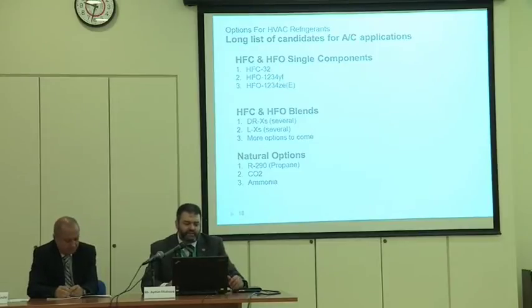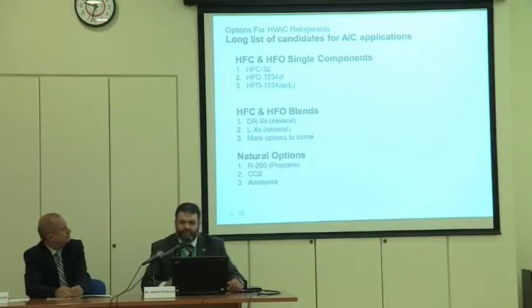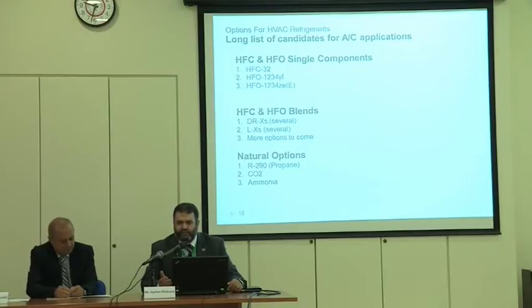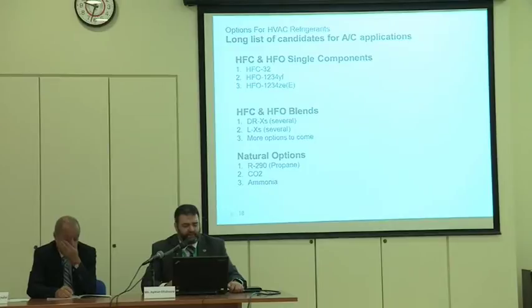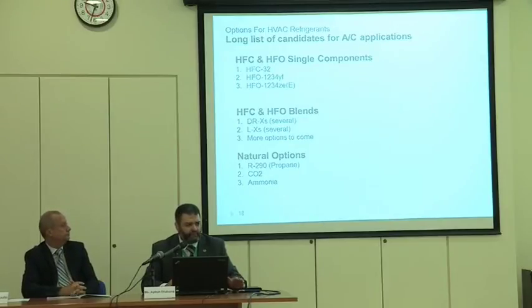The second group is a combination of HFC and HFO blends. HFOs are called hydrofluoroolefins — a new group invented by refrigerant manufacturers that has less atmospheric life, so it has very low GWP impact, most likely between 500 and below in most cases. They don't have R numbers yet. They're being introduced under commercial numbers by 2 to 3 companies across the globe — DR numbers, L numbers, and other options. All of them are still under examination; none of them have yet been put to real production in any industry worldwide.